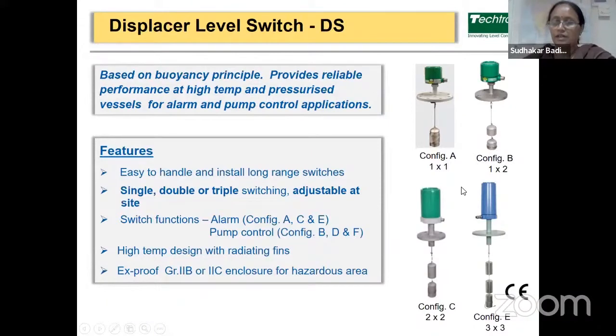So other than that, combinations of these various configurations B and C are available. You can refer to our catalog also. This is easy to handle and install for long range switches. It is available up to 15 meters range. Single, double, and triple switching, which are adjustable at site. Switching functions can be alarm switching functions or pump on or off functions, or pump control application also there. The high temperature design is available up to 300 degrees Celsius with radiating fins. Then Ex-proof enclosures with group 2B or 2C are available for hazardous area applications.